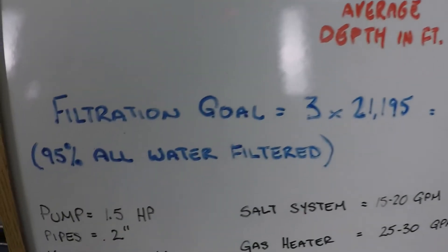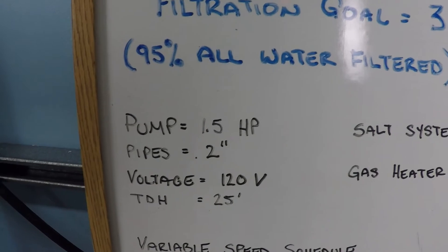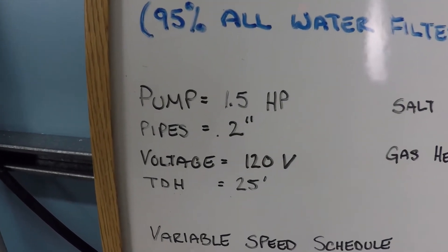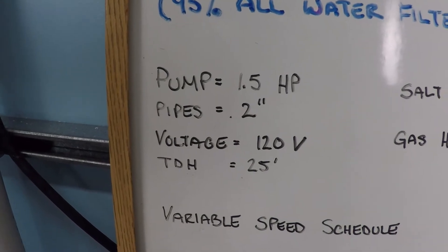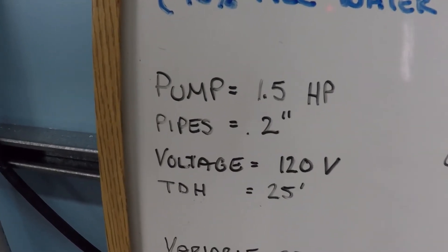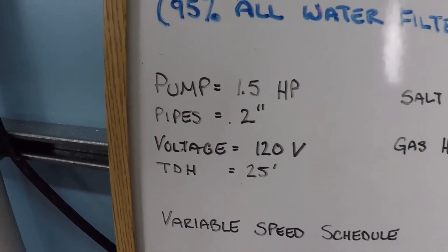So here's some of the parameters we're working with on this pool. One and a half horsepower pump, two inch plumbing size. The pump is installed at 120 volts and the TDH is relatively low at about 25 feet.